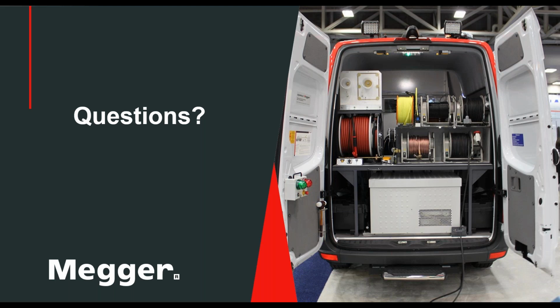My answer to this was that it depends on the breakdown voltage of your particular fault, and if the breakdown is higher than the SmartThump range, a larger unit will be needed. But as a side note, the unit's voltage range is worth a shot using because you don't know the breakdown voltage on these 69 to 230 kVs. We've had multiple customers who have tried using these ST25s on these higher ranges, and depending on what it actually breaks down at, if it breaks down earlier than 25 kV, you can use this unit.